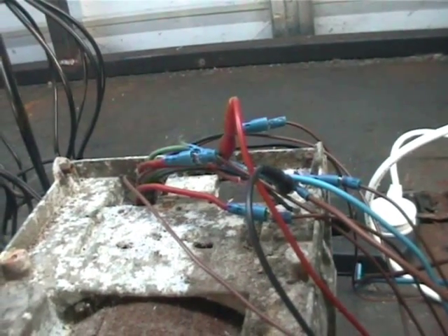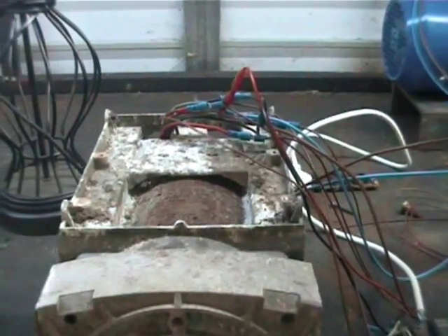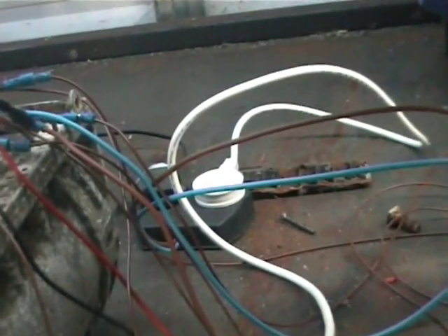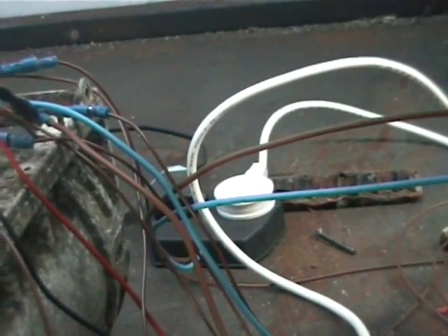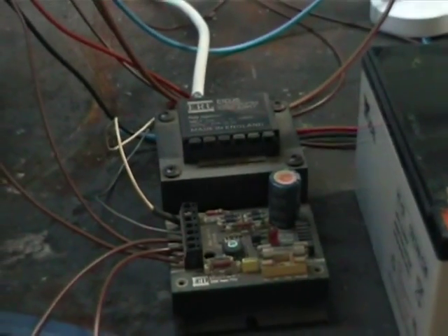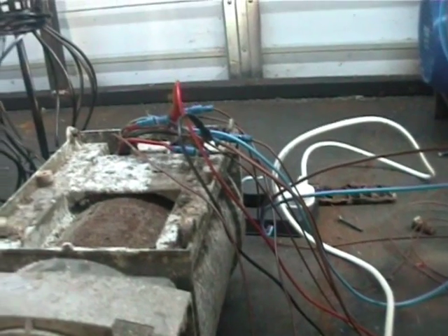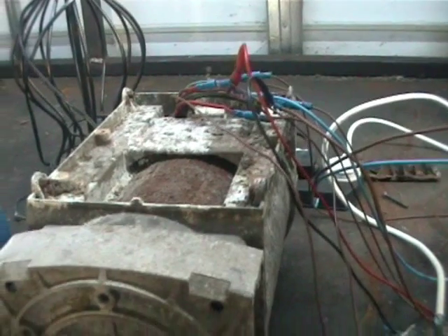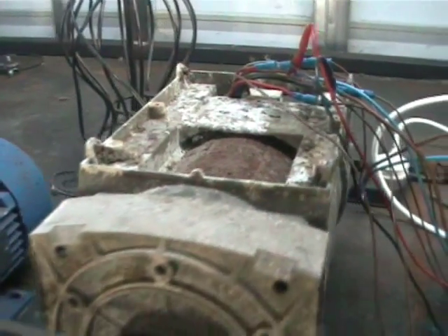This is actually a 3-phase generator head, and we've set up a system so that it takes some of its own generated power back and feeds it through this power supply, which translates 240 volts AC 50 Hertz into 24 volts DC. This feeds back into the brush box and goes into the rotor, providing the magnetic field that we need to generate power.